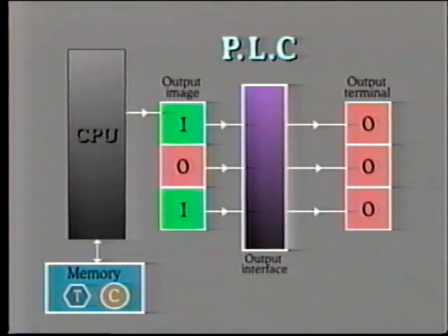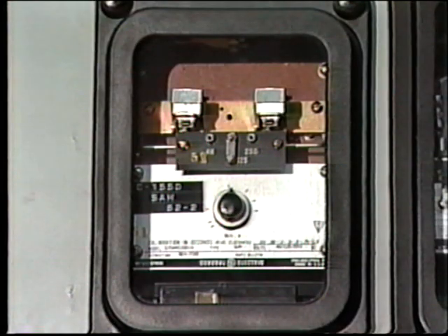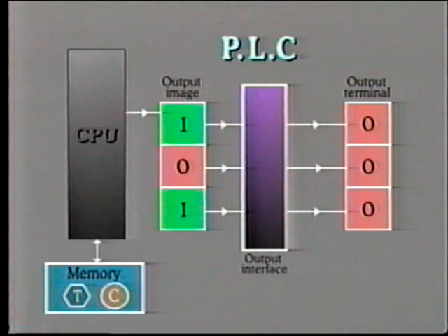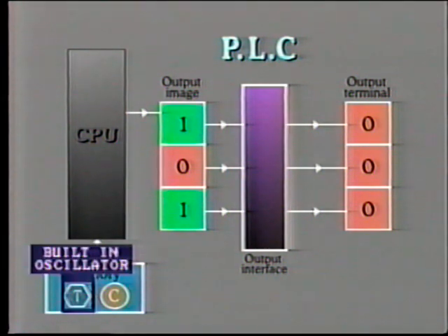These functions are actually contained within the computer software. So instead of having to energize an external time relay, which would then initiate the on signal, all of this activity can be performed within the PLC. The timer obtains its signal from a built-in clock oscillator. The counter works by counting digital pulses.